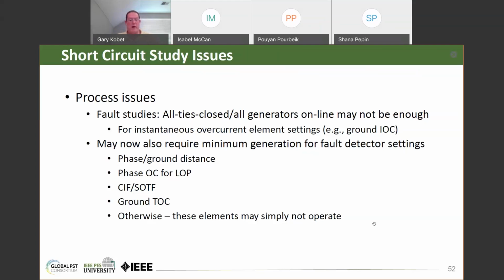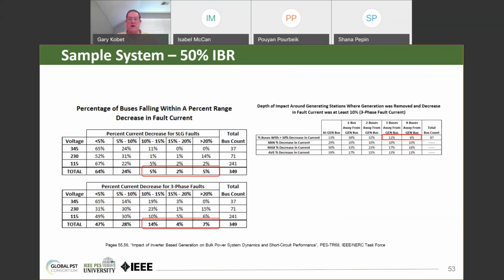Next slide. The paper goes into three different sample system studies where conventional generation has been replaced with inverter-based resources. One study has 50% IBR where there used to be 100% synchronous. And the bottom line here is that very near those locations where there used to be synchronous generation, where there's IBR now, you may have sensitivity issues at those sites, and that kind of makes sense. The further you get away from those, and further toward where the synchronous generation remains, there isn't as much of an issue. But all these things have to be taken into account. So there are three different case studies in the paper, and I'll refer you to that for more details.